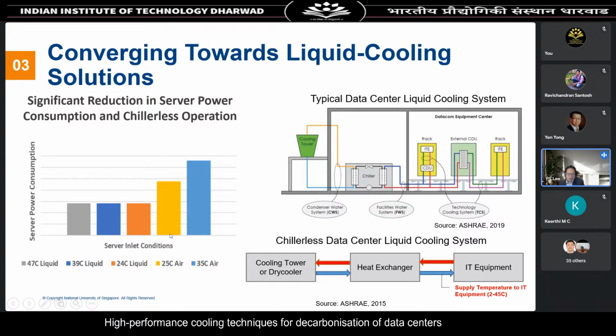If you look at air cooling, let's use 25 degrees inlet air cooling as a baseline. If you increase the supply or inlet temperature for air cooling from 25 degrees to 35 degrees Celsius, you'll notice a server power consumption penalty, because operating your chip at elevated temperature means it operates less efficiently. But if you look at liquid cooling, at the lowest inlet liquid temperature of 24 degrees, compared to the baseline of 25 degrees air cooling, there's a very substantial reduction in terms of server power consumption.